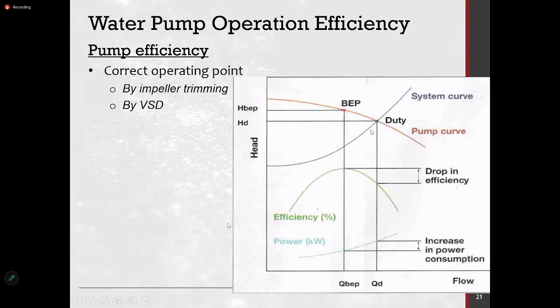But nowadays you actually look at a pump curve and then select a proper pump. So this is your system curve with the flow and the head. And this is your pump curve. So you select a pump curve to coincide with the system curve. And this is the efficiency for this pump curve.